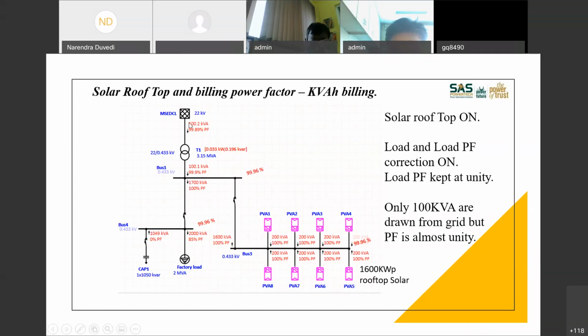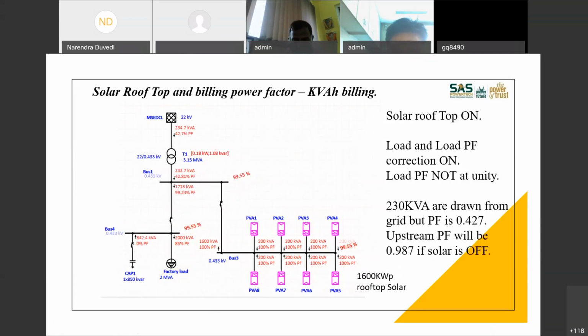So again, my metering power factor will still remain at 99.89 because the reactive power requirement of the load is totally compensated at the plant itself. I am not expecting anything from the grid at present, so it will not affect my metering power factor as such. Now let us see where I have reduced correction. Instead of 1050 kVAr, now I have made it 850 kVAr. So the load is still the same, but now my load is drawing power at 99.24 PF.